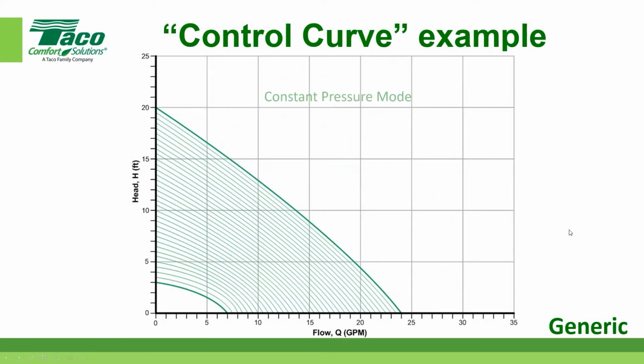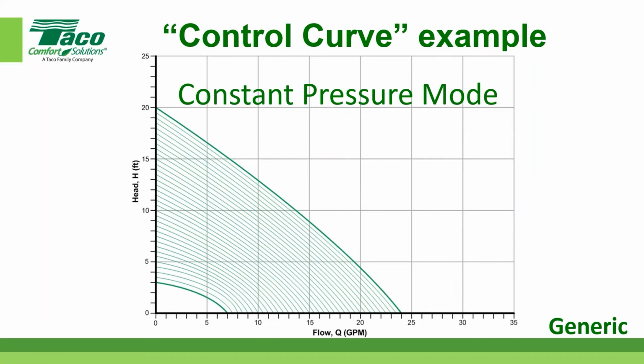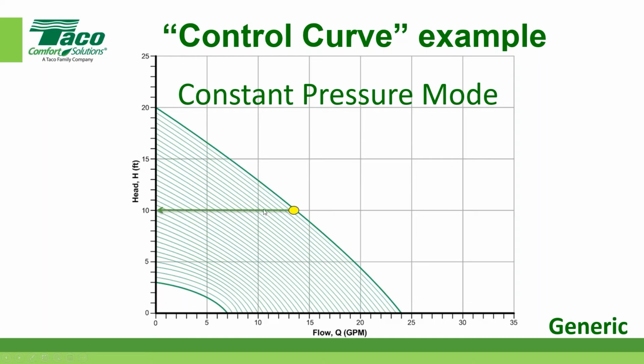Lastly, we talked about the control curve, and that's real simple. That gets us up into variable frequency drives or ECMs, the high efficiency pumps, when somebody might use this term. I like to call it an operating range, so it's not one more curve that somebody's going to get confused by. This would be in a constant pressure mode. We're showing you from here, it's just going to move back this direction. Again, when I'm teaching it, I'm calling it an operating range, not a curve. These are curves, because generally speaking they're curved, and the system comes up here in a curve pattern. This is just a range of operating conditions.